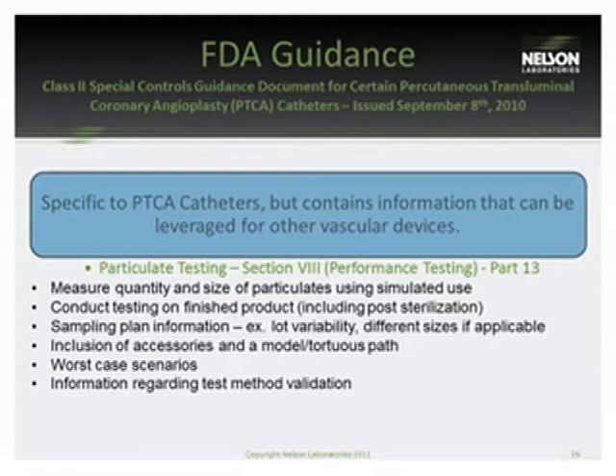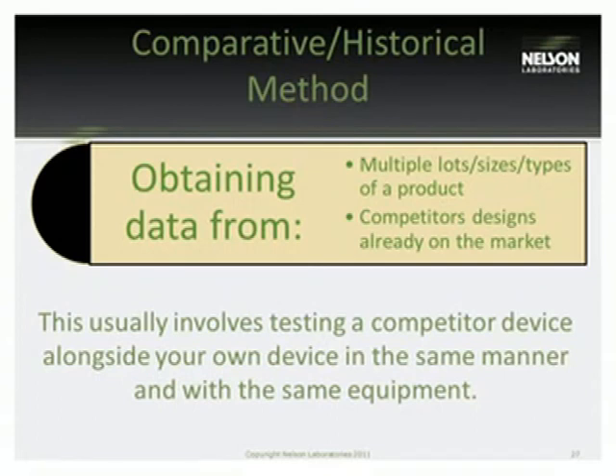Now, speaking a little bit more of comparative and historical data, obtaining data from multiple lot sizes and types of a product, as well as competitor designs already on the market, has a great deal of value in doing particulate matter testing. Mostly because you're getting a significant amount of data from your device as well as competitor devices, which can show justification very well for the safety of your product, which is ultimately the point of the submission to regulatory.